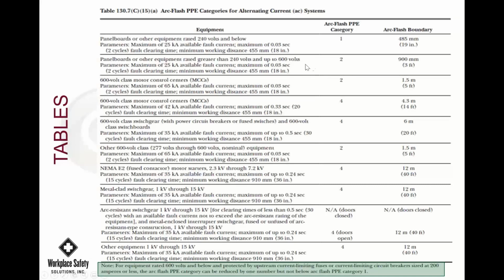If you are within that range, then you could go with category 2, and you have a 3-foot arc flash boundary. So you can use this if it's within the parameters. That's the problem with this. People are using this table and not following the parameters. The arc flash analysis I showed you was 76 calories. If you look on here, working on that switchgear with 35,000 amps, it's a category 4. Well, you can't wear a category 4 because it was 76 calories, and the reason is that it exceeded 35,000 amps. That's why you have to look at that level and make sure you follow those sections.